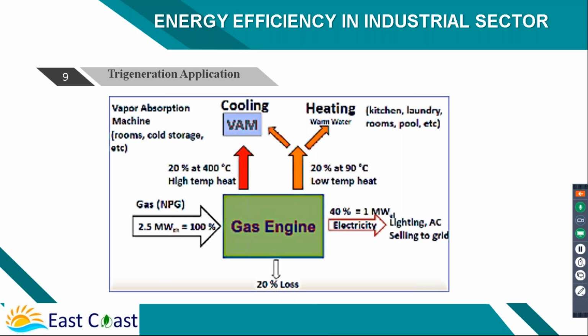The gas engine or diesel engine efficiency is only 40%. So if you want 1 megawatt power, you have to give 2.5 megawatt input. So what is happening to the other 60%? 20% will generally go as waste heat through exhaust, engine exhaust, which may be at 250, 300 degrees, whatever, or sometimes bigger. If you don't have any other heat recovery, it can be 400 degrees also.